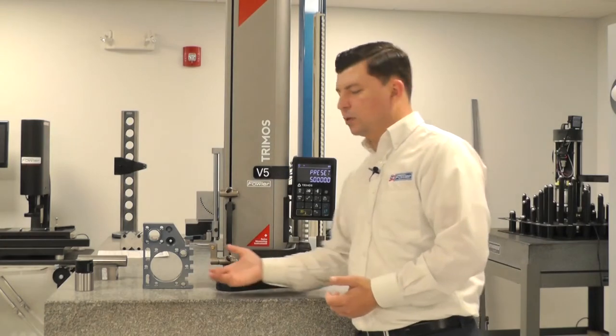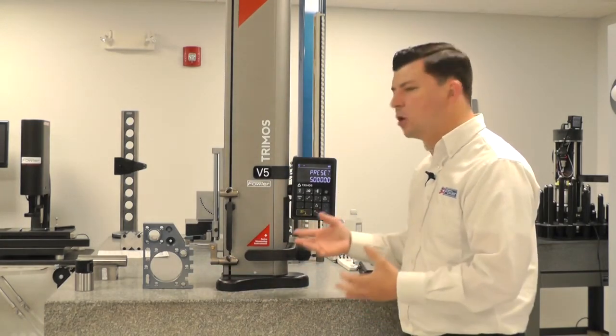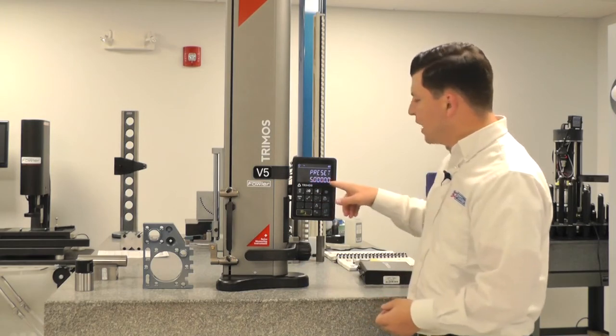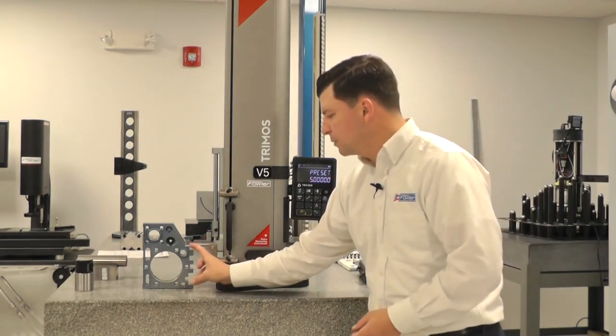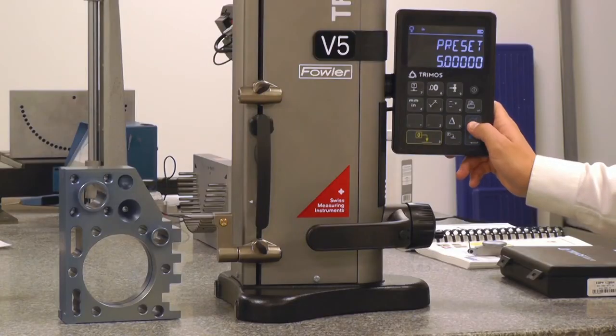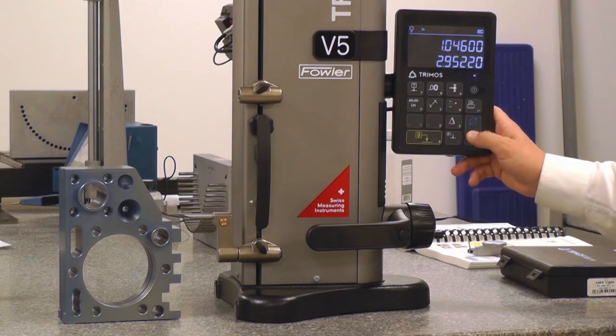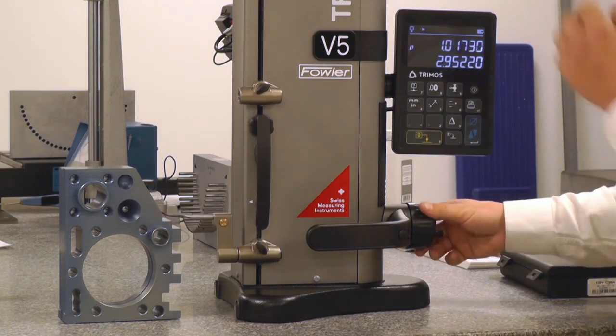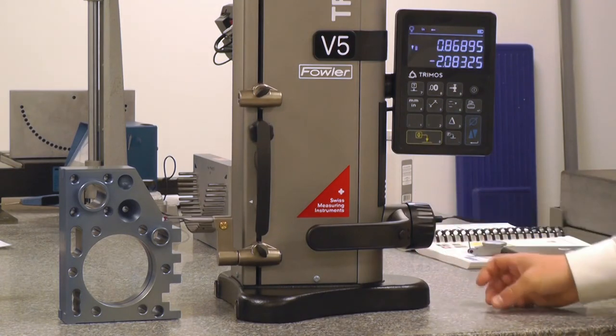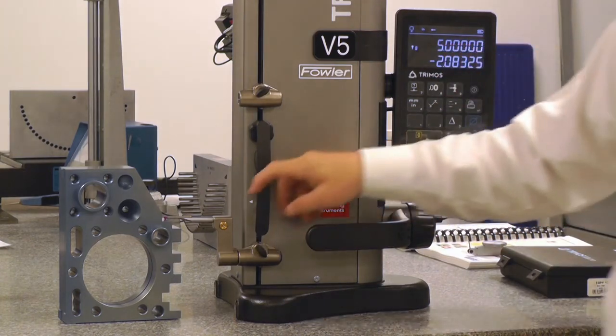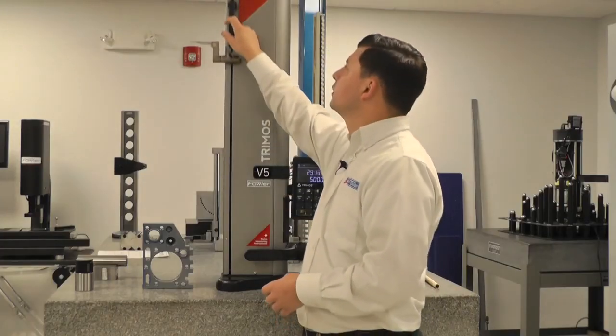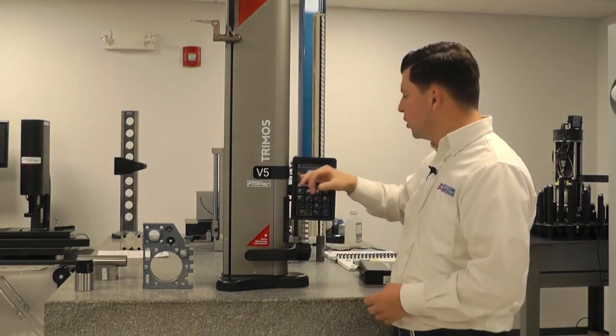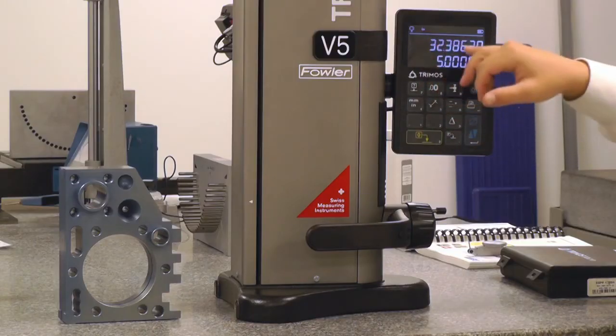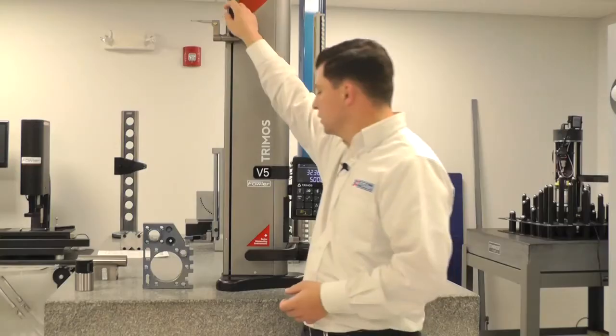That's the value that I'm going to preset off of whatever known height you have. Typically, you're going to just use a set block, but any known height you have will suffice. So a 5-inch gauge block, that's perfect. This is our make-believe 5-inch gauge block. So we'll save that by holding down our blue button. Then we'll come over to our gauge block, engage the probe, just tap our preset button to establish that 5 inches. And now if we run our carriage all the way up through our measuring range, we're no longer at 28 inches, but we're at 32 inches and 32 inches plus.